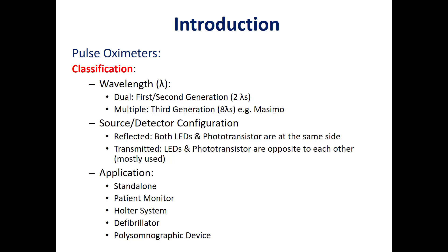One classification is according to the number of wavelengths. We can have the pulse oximeter which uses two wavelengths, known as the first and second generation.